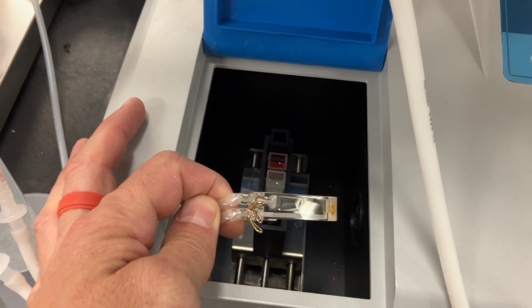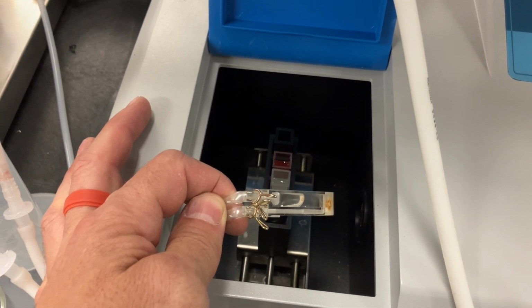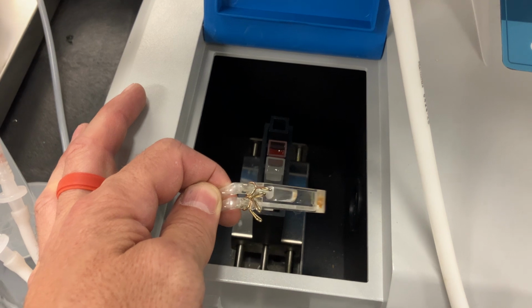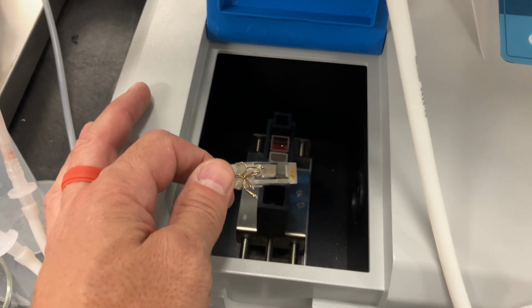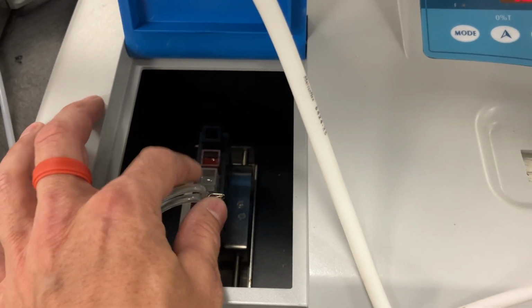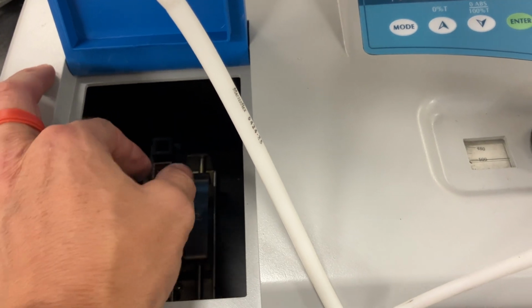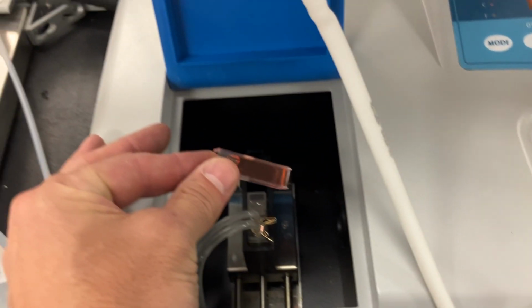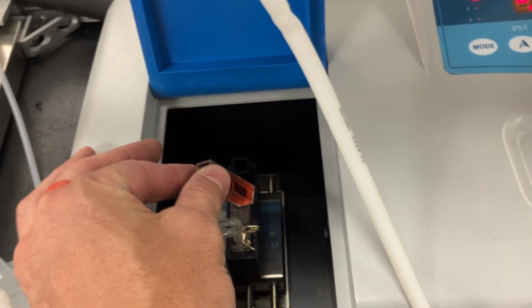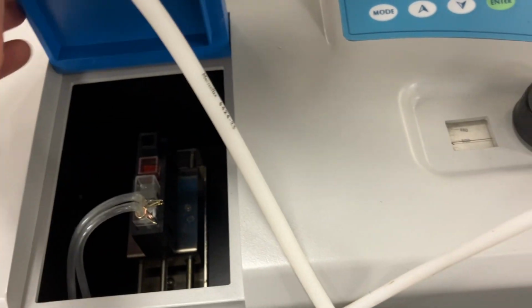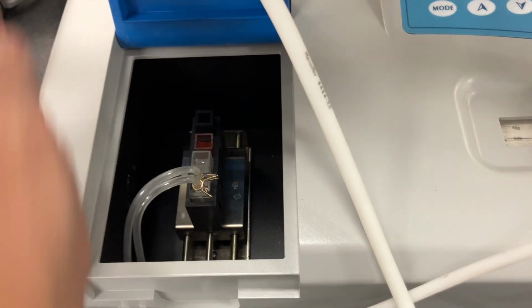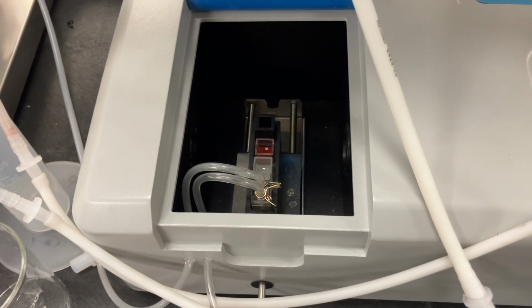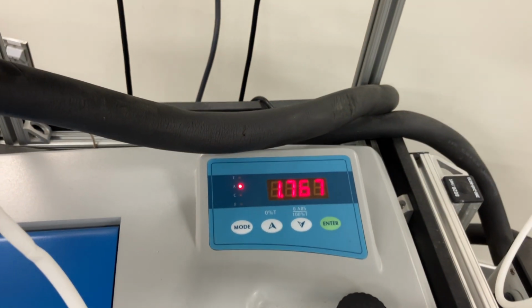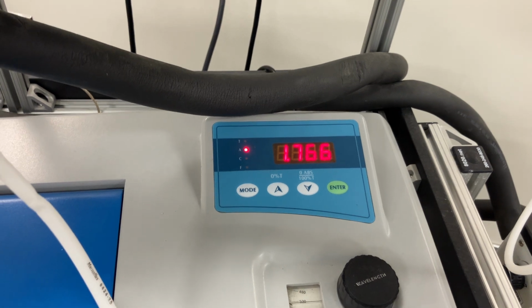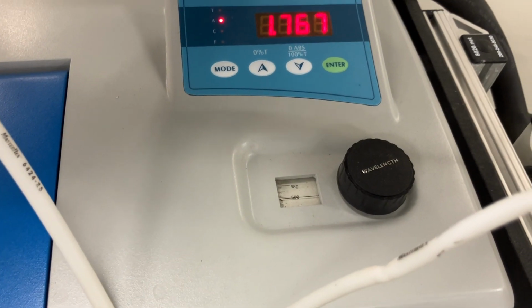Notice there's a port that goes all the way to the bottom and then comes back out the top, and you want to make sure this doesn't have any air bubbles in it. And then there's also this one here that I've got that's just full of red dye. Now I'm going to index it in this case just to the red dye port, and it should read about 1.7-ish around there at 510 nanometers.